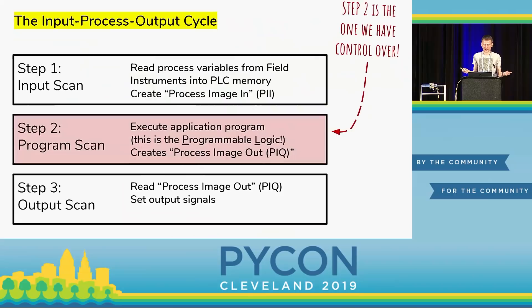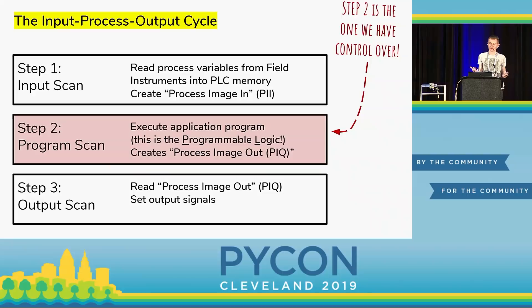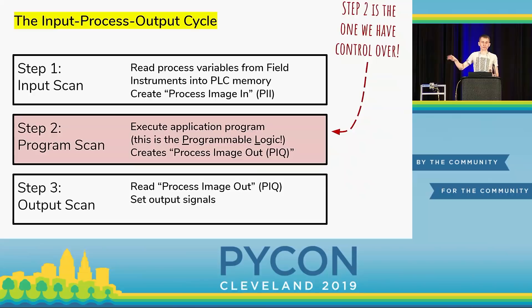A PLC goes through the IPO cycle like any compute device. In the first step, input, we read the process variables from the field — the PLC looks at electrical signals and stores them in memory in a place called the process image in. In step two, we run some logic and computation, turning input variables into output variables, written to the process image out. The PLC then turns those variables into electrical signals to our actuators — a motor, a fan, whatever we're controlling. The interesting bit is step two, because that's where the programmable logic lives and where we can have an effect.